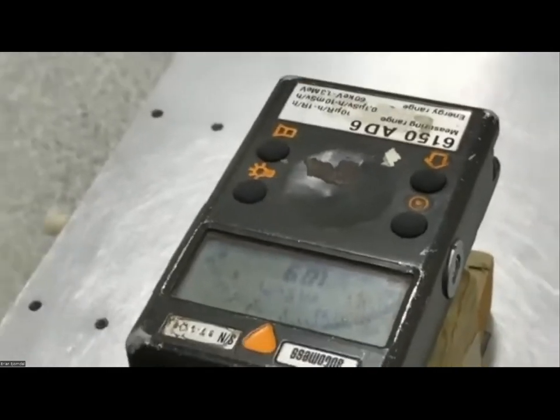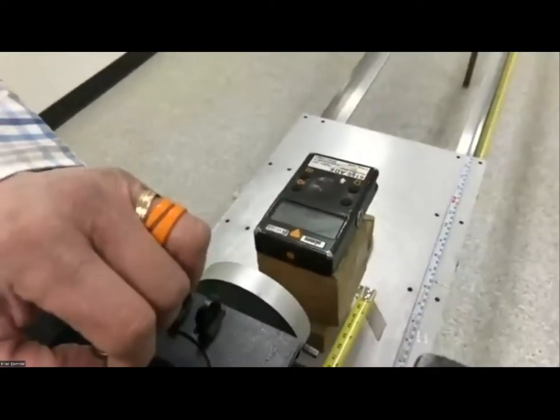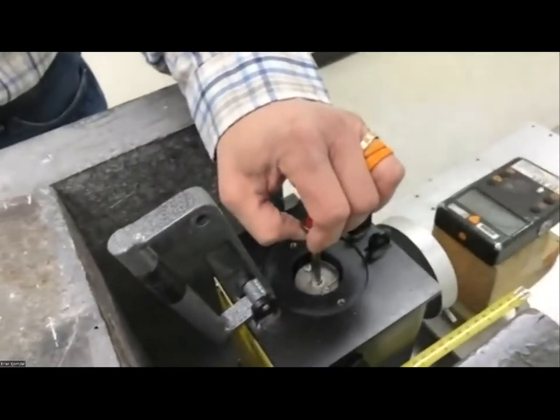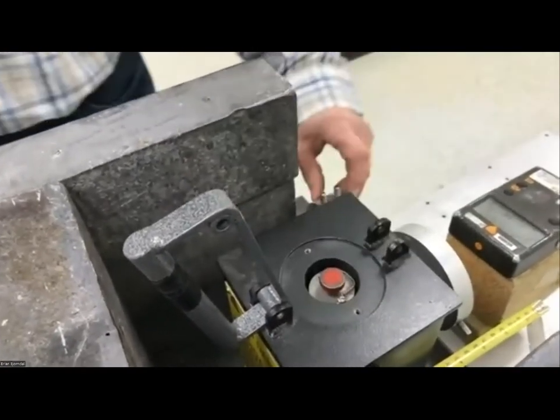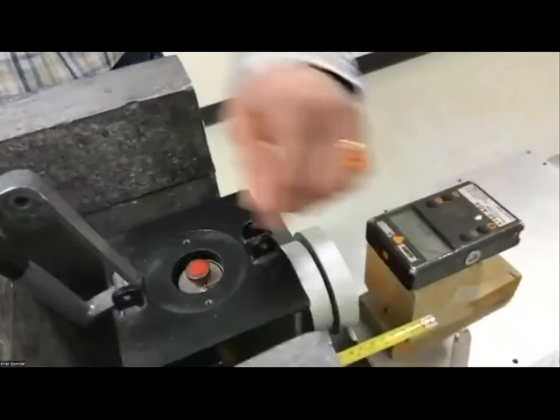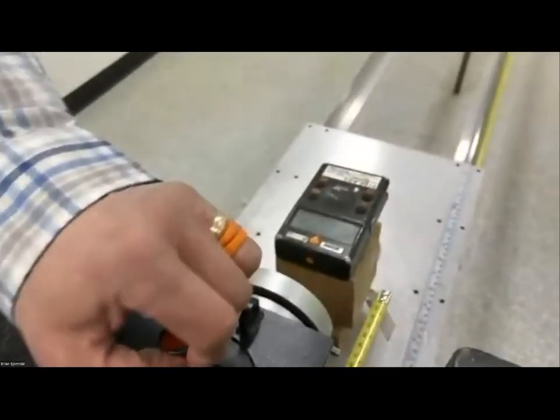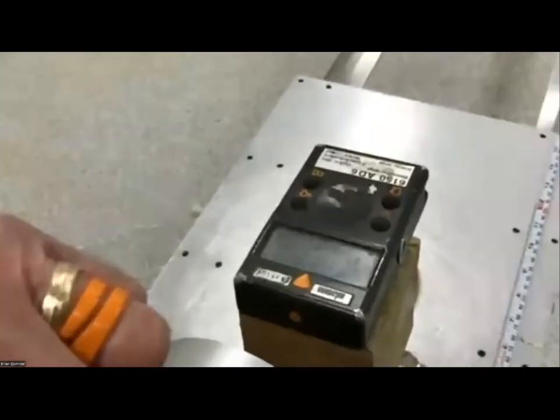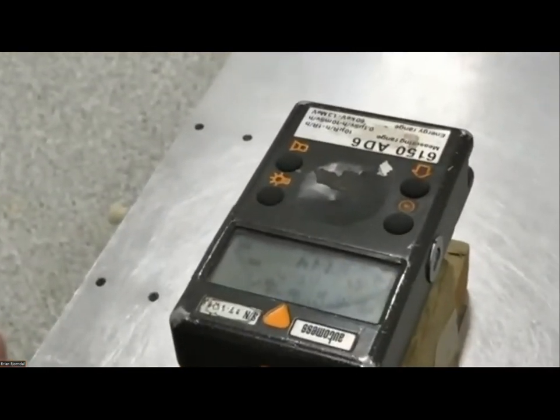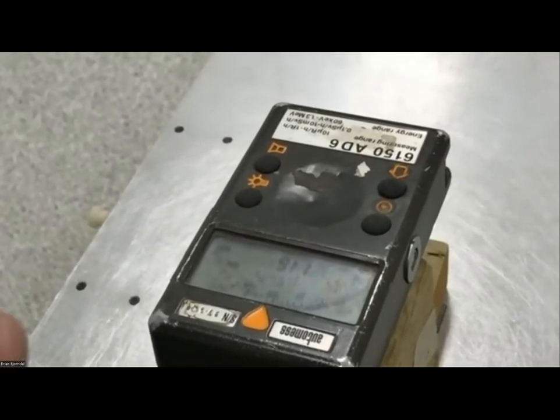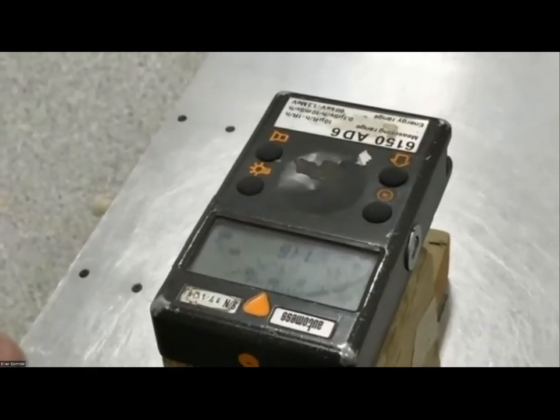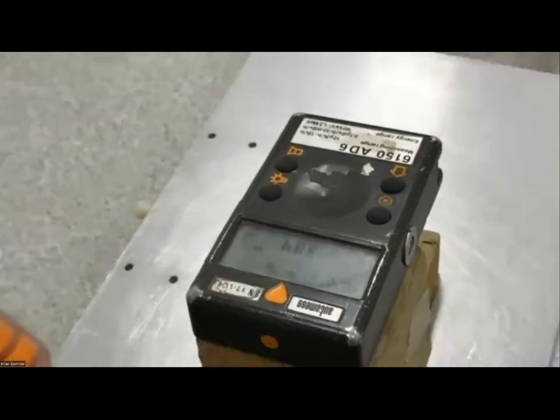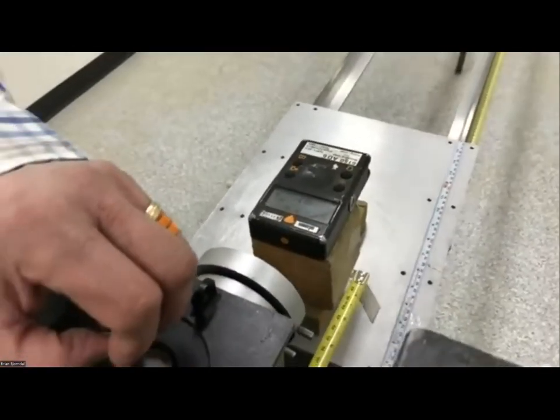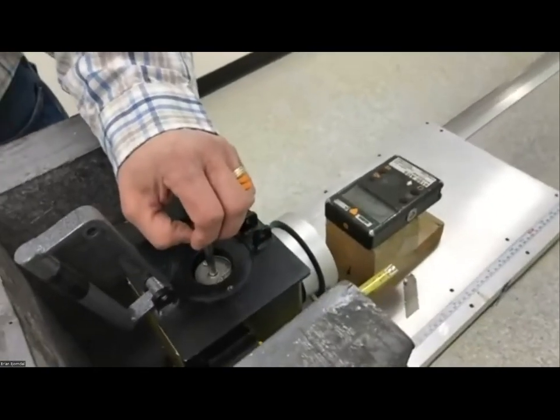Now, I should add, before we start, we do background measurements on these, and we log that data as well. So this process continues. The technician will take that reading, then drop that plunger, and introduce another times 10 attenuator. Again, they'll lift the plunger, let the beam stabilize, let the instrument stabilize, and take the reading. They continue to do that through a number of different settings and collect the data. What we're looking for is agreement with the source at that desired distance and dose rate within 20%.